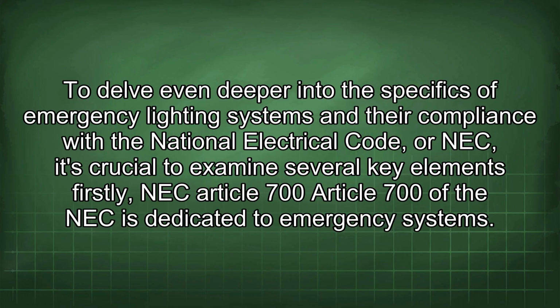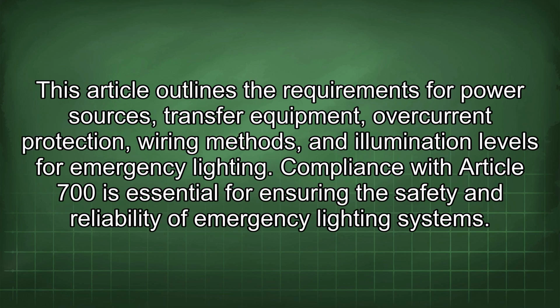To delve even deeper into the specifics of emergency lighting systems and their compliance with the National Electrical Code, or NEC, it's crucial to examine several key elements. Firstly, NEC Article 700. Article 700 of the NEC is dedicated to emergency systems. This article outlines the requirements for power sources, transfer equipment, overcurrent protection, wiring methods, and illumination levels for emergency lighting. Compliance with Article 700 is essential for ensuring the safety and reliability of emergency lighting systems.